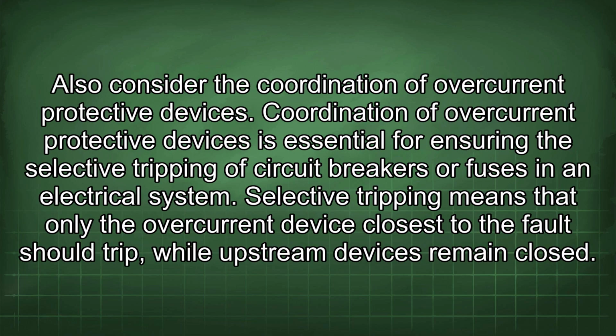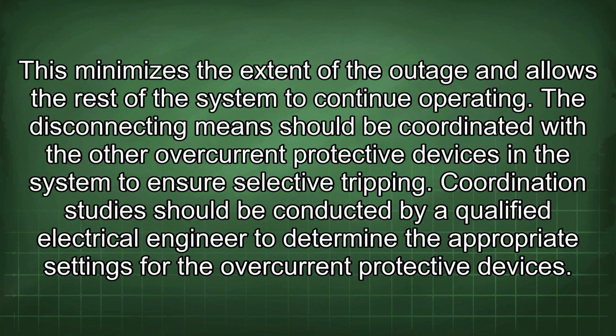Also consider the coordination of overcurrent protective devices. Coordination of overcurrent protective devices is essential for ensuring the selective tripping of circuit breakers or fuses in an electrical system. Selective tripping means that only the overcurrent device closest to the fault should trip, while upstream devices remain closed. This minimizes the extent of the outage and allows the rest of the system to continue operating. The disconnecting means should be coordinated with the other overcurrent protective devices in the system to ensure selective tripping.